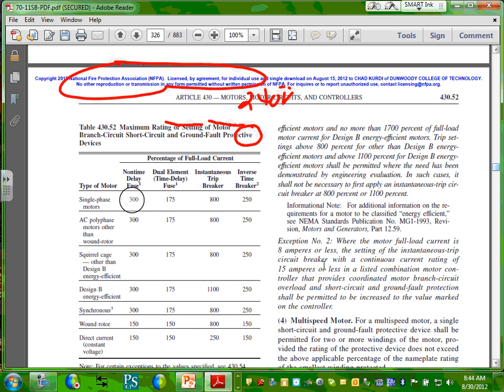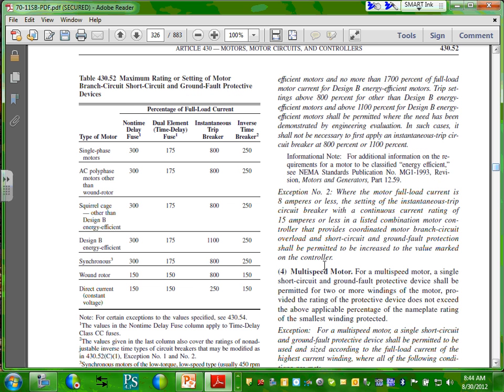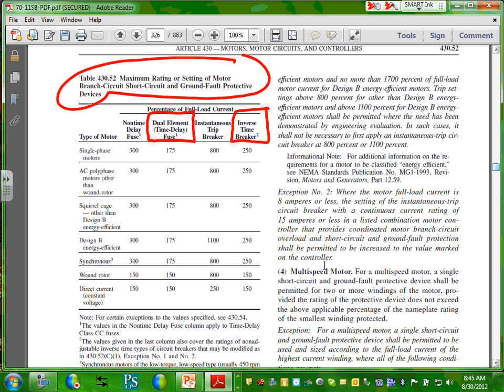If you guys have not been there, please go there and highlight it. We're going to be using this table all over the whole year, basically, because that's what we size. We are the engineers, we size it. Everybody's there? Okay. This is the table that we use to size the overcurrent protection device. In dwellings, 99% of the time, there are 4 types of overcurrent protection device. You're going to be using either an inverse time circuit breaker, or a dual element time delay fuse, or actually a non-time delay fuse. We'll talk about fuses when we go to commercial industrial. Right now I'm protecting it with an inverse time circuit breaker that looks exactly like the ones you have right here. That's exactly what an inverse time circuit breaker is.